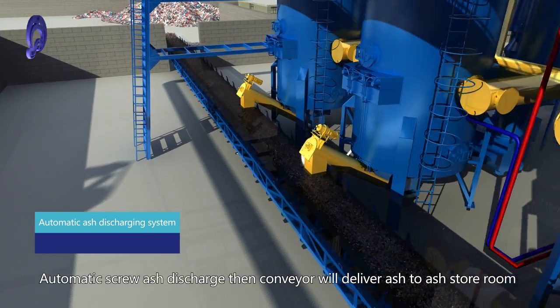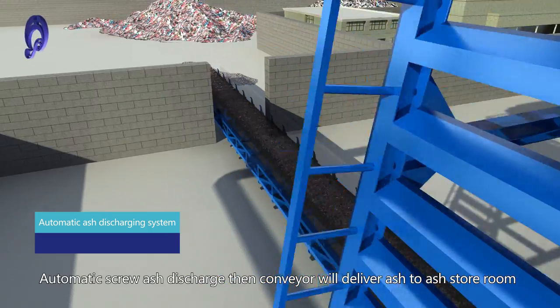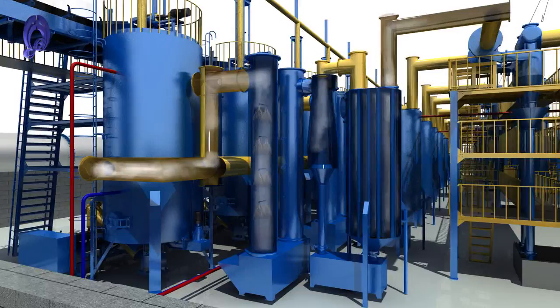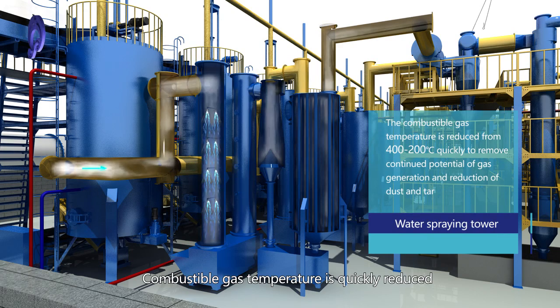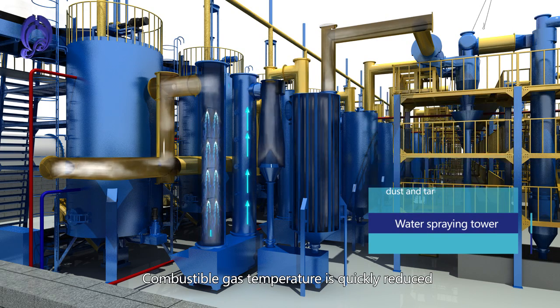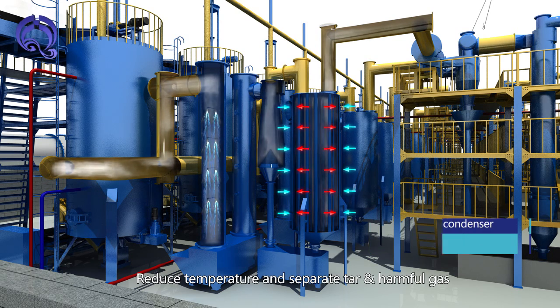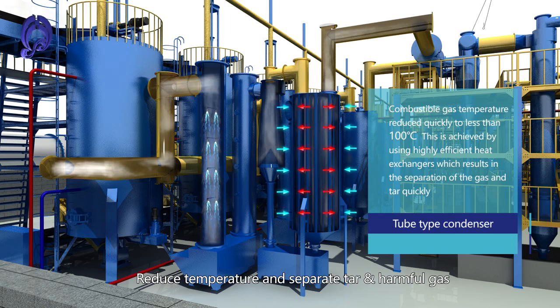The automatic ash discharging system uses an automatic screw ash discharge, then a conveyor delivers ash to the ash store room. A water spray tower quickly reduces combustible gas temperature, followed by a Cyclone Dust Collector to remove dust, and a Tube Condenser to reduce temperature and separate tar and harmful gas.